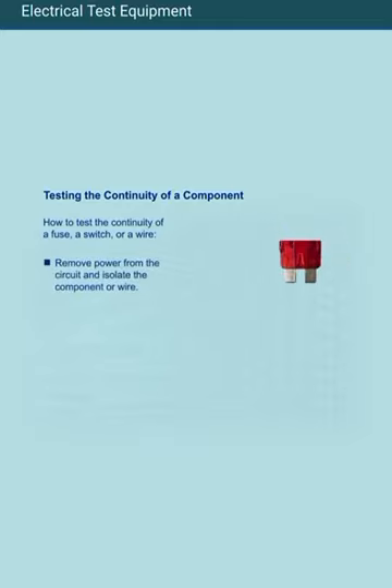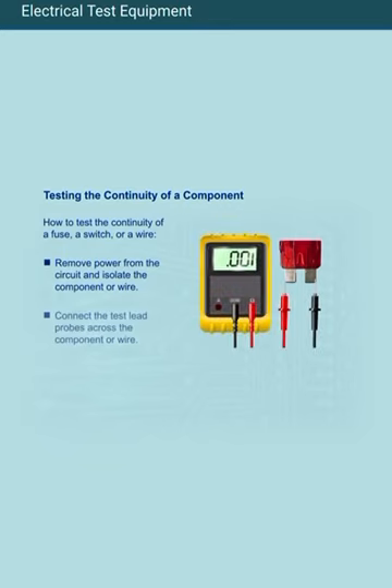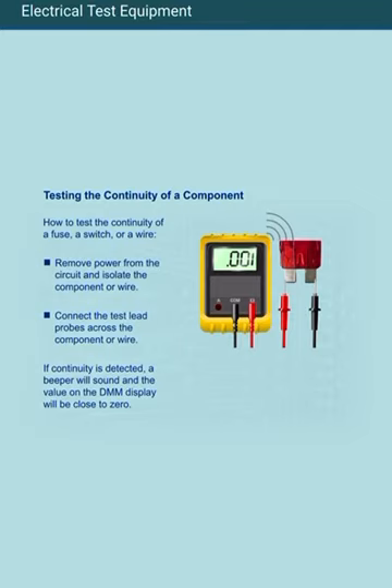Testing the continuity of a component. How to test the continuity of a fuse, a switch, or wire. Remove power from the circuit and isolate the component or wire. Connect the test lead probes across the component or wire. If continuity is detected, a beeper will sound and the value on the DMM display will be close to 0. If continuity is not detected, the display will show an out-of-range indication.